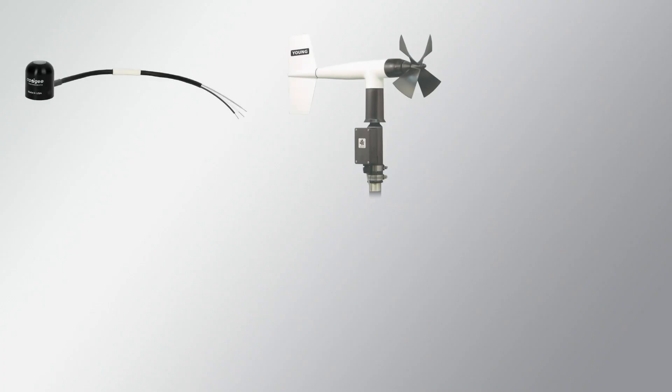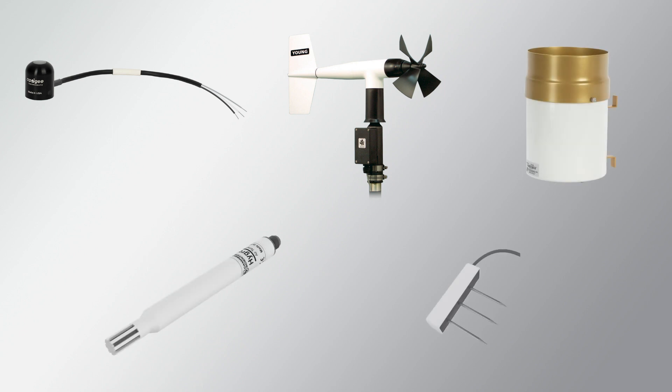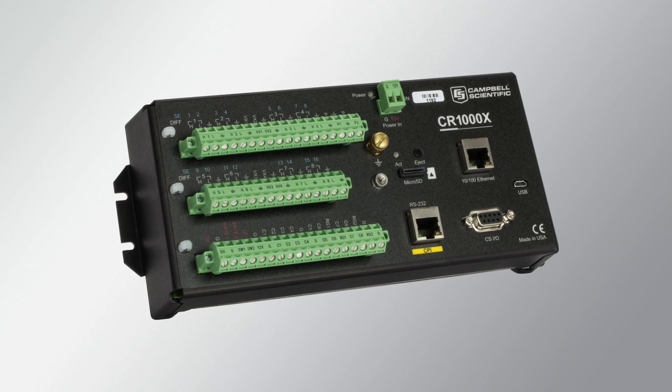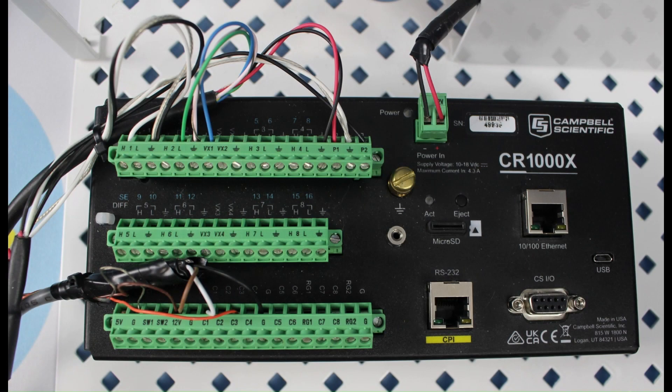Before I can create a wiring diagram to match an existing program, I need to know what sensors are connected to the datalogger and the colors of the individual sensor wires. I also need to know which channel on the wiring panel each wire is connected to. If that information is not available, I may need to make a site visit to take notes and photos of the system.